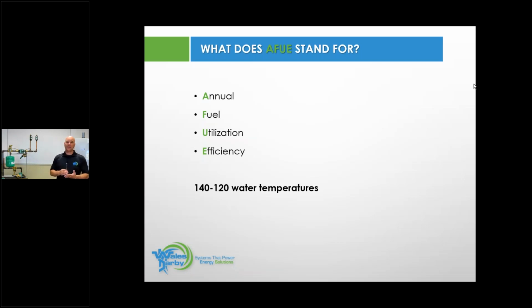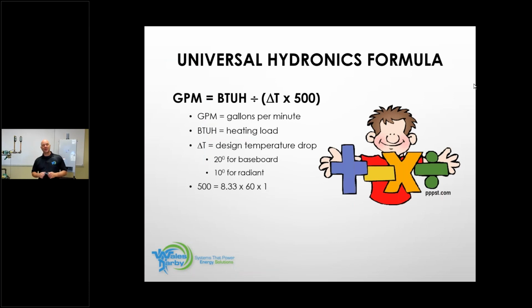AFUE, AFUE ratings. This is the annual fuel utilization efficiency. Those tests are done at 120 and 140 degrees. So when you see all of these condensing boilers out there telling you that they're 92, 93, 94, 95% efficient, they are at those temperatures. But as we start to accelerate those temperatures up, the efficiency will drop. If we bring those temperatures down, the efficiency will actually go up a little bit. You can get close to 98% efficiency with lower water temperatures. So we want to make sure you're 100% up to speed on how this works and what's behind the numbers.